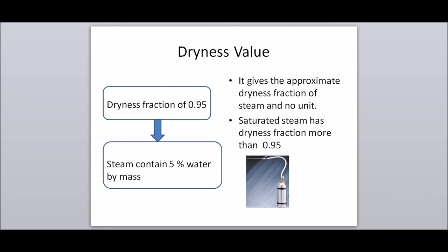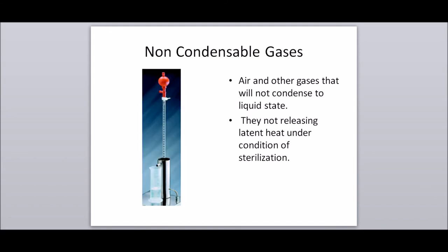Dryness value: it gives the approximate dryness fraction of steam, with no unit. Saturated steam has a dryness fraction greater than 0.95. If we consider a dryness fraction of 0.95, it means the steam contains 5% water by mass. Non-condensable gases: air and other gases that will not condense to a liquid state. They do not release latent heat under sterilization conditions.